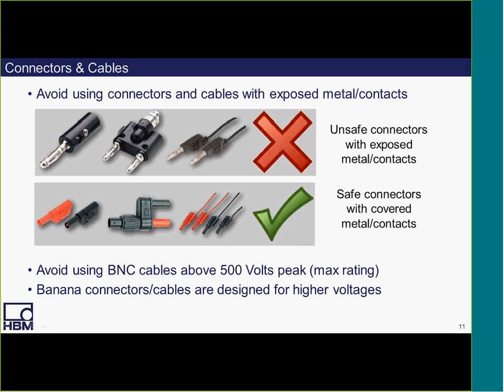Just a quick note on connectors and cables. You want to avoid using connectors and cables with exposed metal contacts, as you see in the box with the red X. The box with the green checkbox, basically those have safe connectors and the metal contacts are covered. And you want to be sure to avoid using BNC cables above 500 volts peak. That's usually their maximum rating, whereas banana connectors and cables are designed for higher voltages.